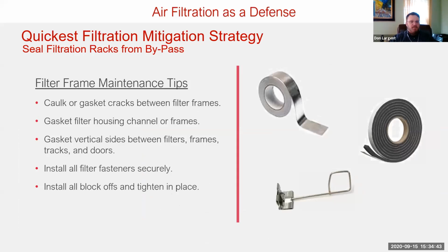Obviously, just your typical routine maintenance and upkeep. Caulk all your seams, tape all your seams, make sure you've got adequate gasketing material, make sure you've got all your spring clips on your filters. I know the air handler unit tends to be the last thing on anyone's checkbox list of things to go check out and inspect and keep up. But these little things will make a very profound difference.